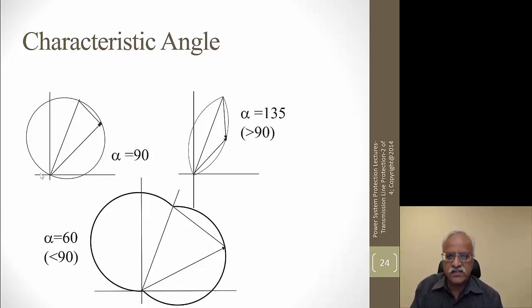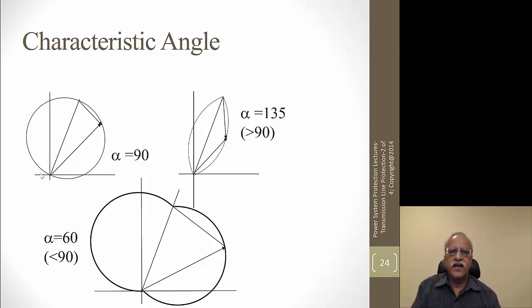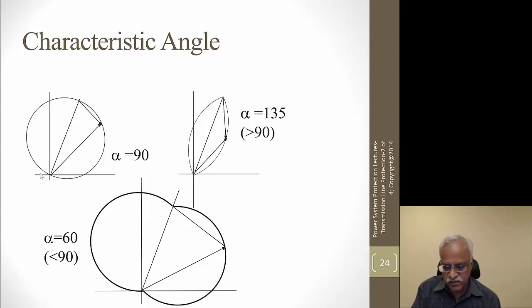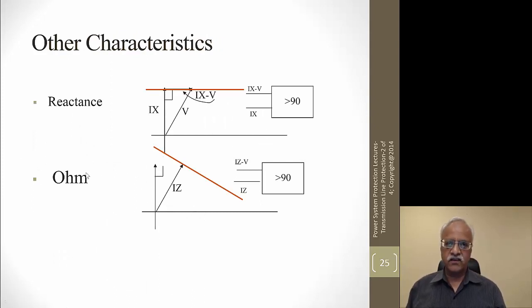To summarize, we have covered these concepts in a short period — please review them again to understand the relay design principles. In microprocessor-based relays, the same concepts are implemented using dot products or cross products — essentially V·I·cosine of the angle — to determine whether that angle is less than or greater than 90 degrees, giving you reactance relays and ohm relays.